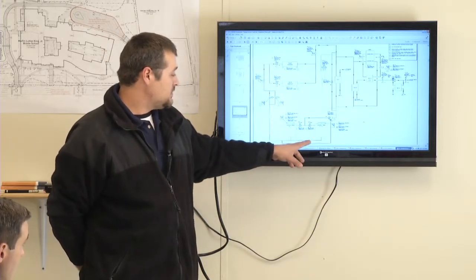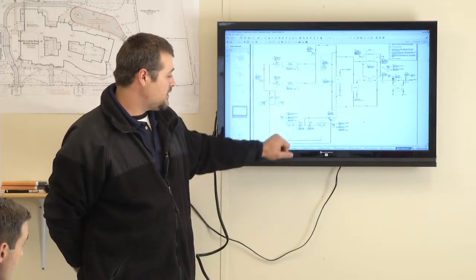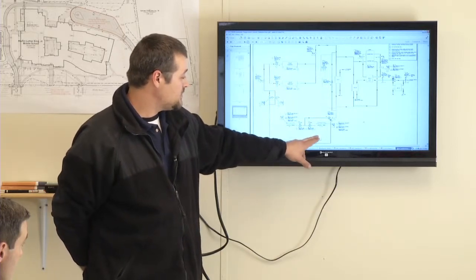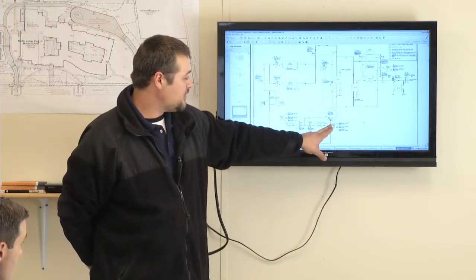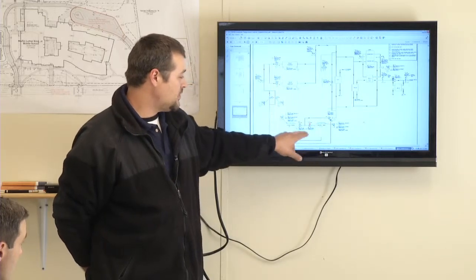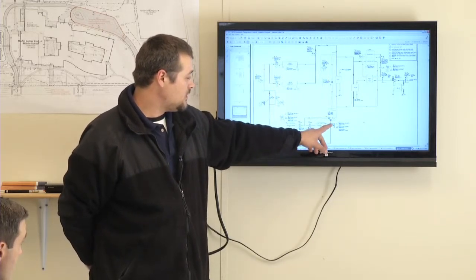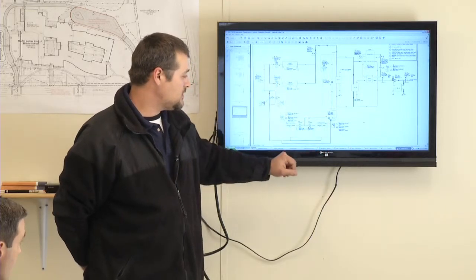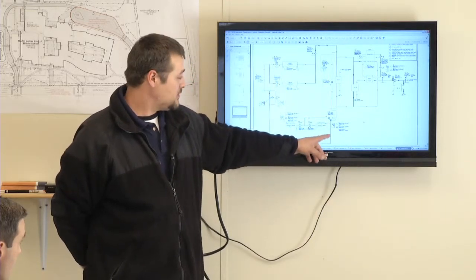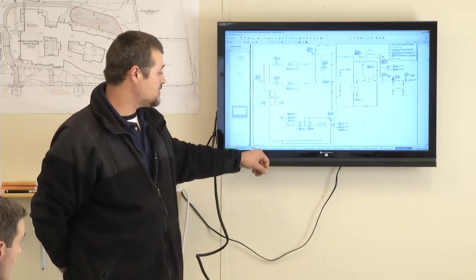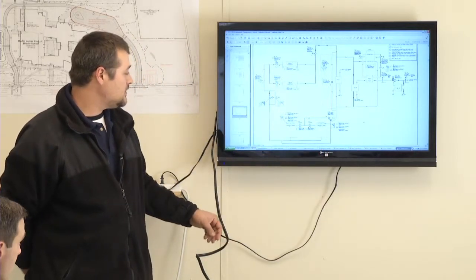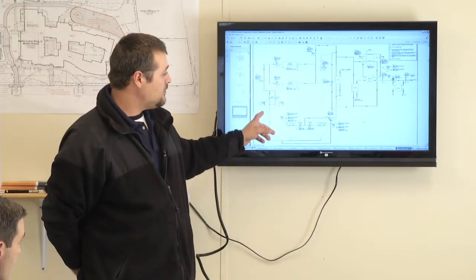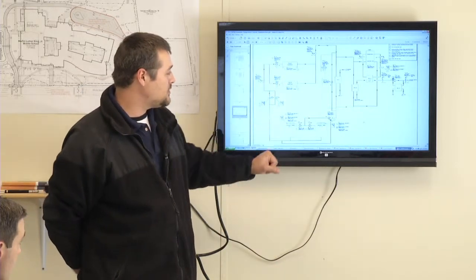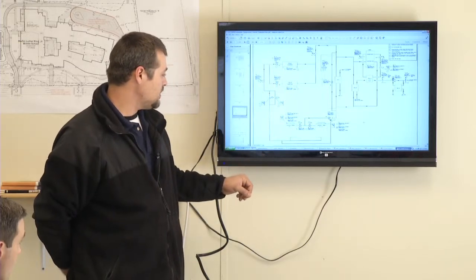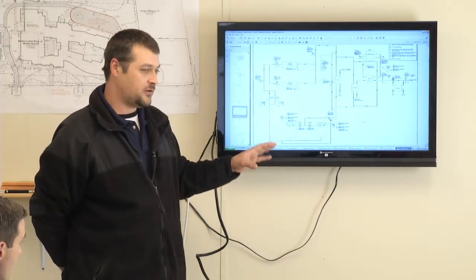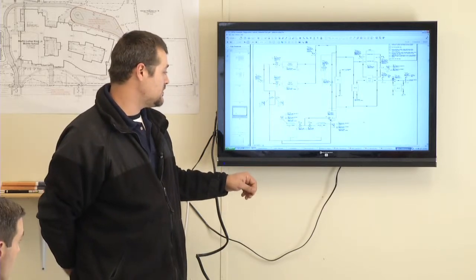Depending upon which unit is operating, we have an isolation valve here to restrict flow to the unit that's not running, and we also have a bypass valve. This valve is normally open to the towers, and in the case where the tower water is too low coming back into the chiller barrel, we'll open this bypass and bypass the cooling tower section. The pump skid houses all of the main pumps except for the inline pumps, which we'll get into in a little bit. The cooling tower drives are in the far right corner of the plant adjacent to the chillers.